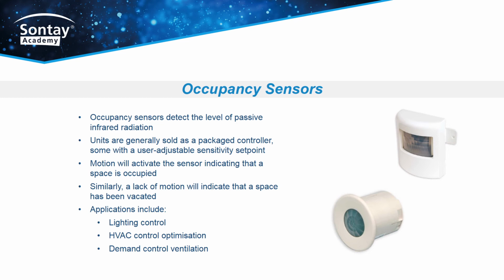By using occupancy detectors, HVAC plant can be operated in a standby mode during the defined occupancy period, but when there is no actual occupancy detected. An example of this would be a fan coil unit serving a meeting room with a temperature set point of 22 degrees C. In standby mode, the unit has a temperature controlled dead band of 4 degrees C, meaning a heating set point of 20 degrees C and a cooling set point of 24 degrees C. Once occupancy is detected in the meeting room, the dead band is shifted to 2 degrees C to improve comfort and is then reverted to standby mode once the room is vacated.